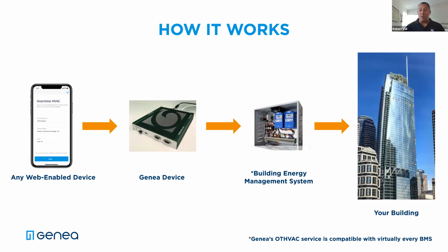In fact, we have an official partnership with Siemens, where if you have a Siemens building and need a service like ours for overtime HVAC, they actually refer you to us. The device goes on site and plugs into the same network as the building automation system. From there, we leverage all the programming already done with your controls contractor - we command a point at a higher priority than the schedule. Service turns on, and when service is rendered, we release the point and the normal schedule takes over. It's very innocuous and easy to implement.